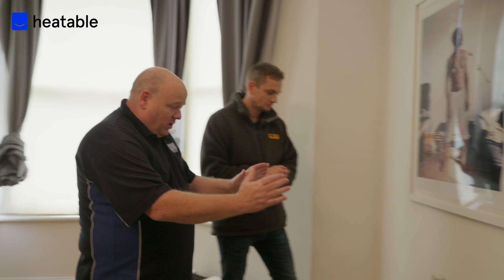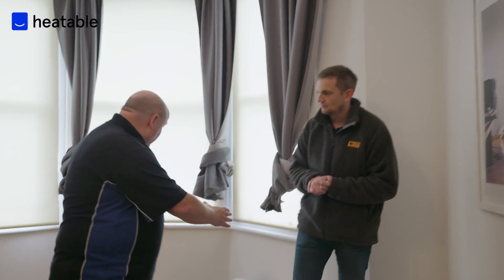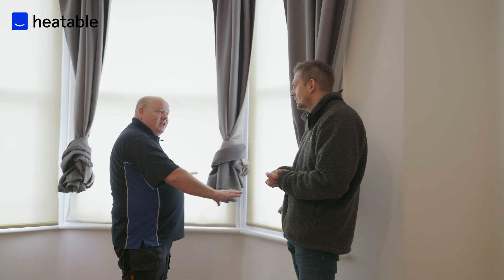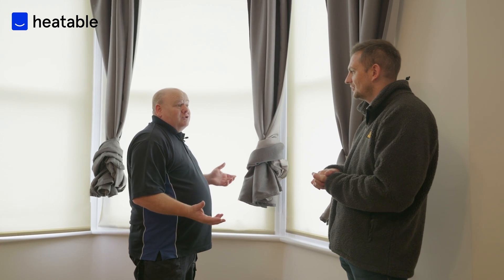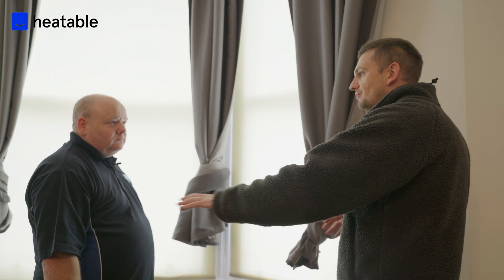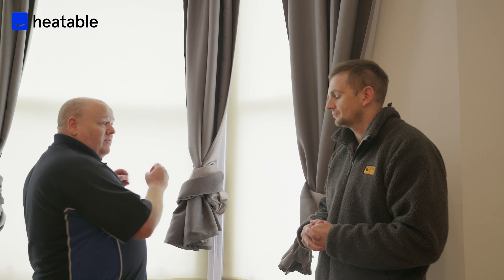We've got an old radiator in here that's been removed — it was only a small one for this room. What we've got now are three fancy designer radiators. Ideally in an ideal world we'd be putting white pressed steel radiators on because they give the best output, but it's also about what the customer wants — you've got to be sympathetic to the property's period features. What we've done is increase the amount of convection by adding more radiators while giving the customer the look they want. We did a heat loss with Alpha and got the best solution we could with the aesthetics the client wanted.